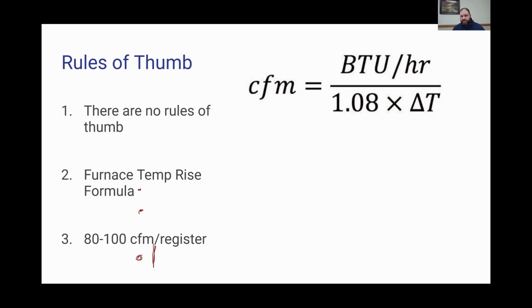However, we still go through the duct system because we can run into things like I did yesterday, where he had 12 registers. So to me, that says 1,200 CFM. He had a furnace that wanted to move 950. So I go, we should be good. 950 is less than the 1,200 CFM we should be able to move. But he had that undersized 8-inch duct feeding half of his house.